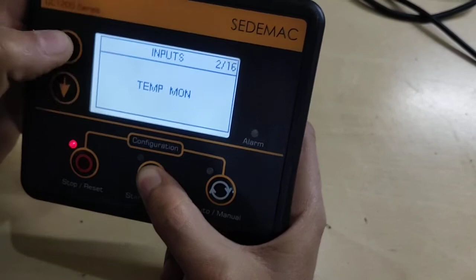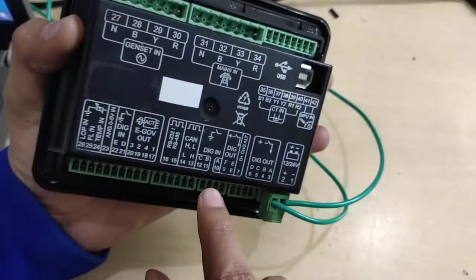You can monitor these functions, like lube oil pressure. What action will it take when lube oil pressure is high or low? It will show a warning, or it will shut down the generator. Then there is temperature monitor, then fuel level monitor, then water level monitor. So all these functions are there, and you can adjust which input function to use according to the parameter here.